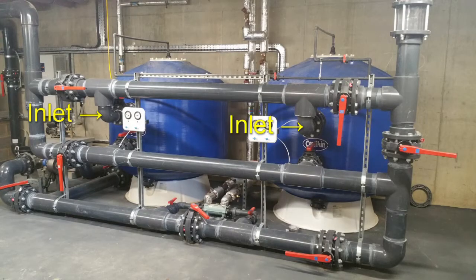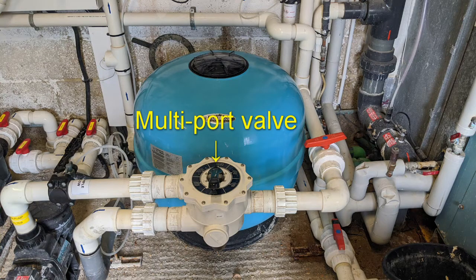Starting at the filters, there'll be pipework going into the filtration system, or into each of the filters if there are multiple filters. So identify the inlet pipework. On a conventional swimming pool filter, it'll be the topmost pipe leading into the filter. If you've got a spa system, that's likely to have a filter with a multiport valve rather than individual valves. So identify where that is and then start moving backwards.